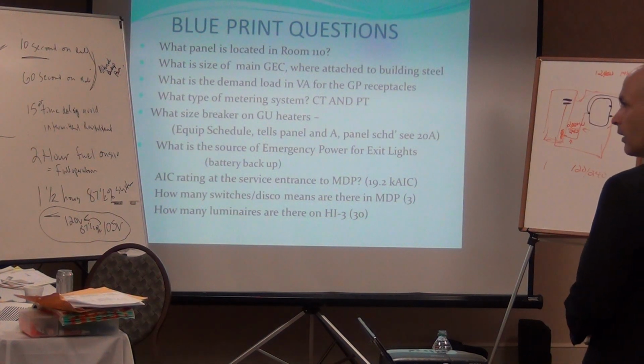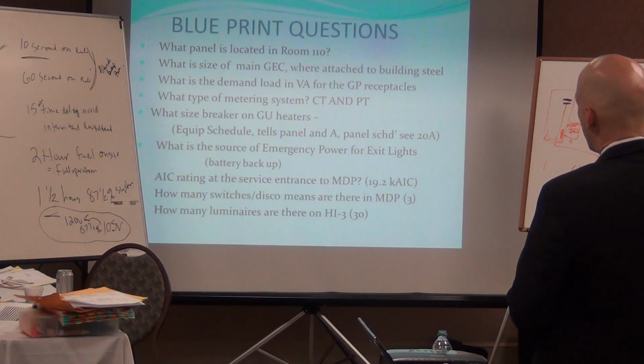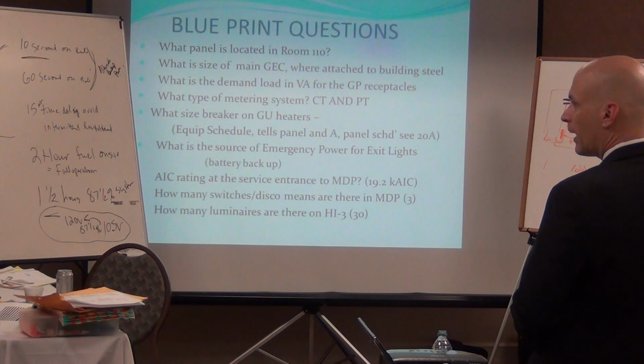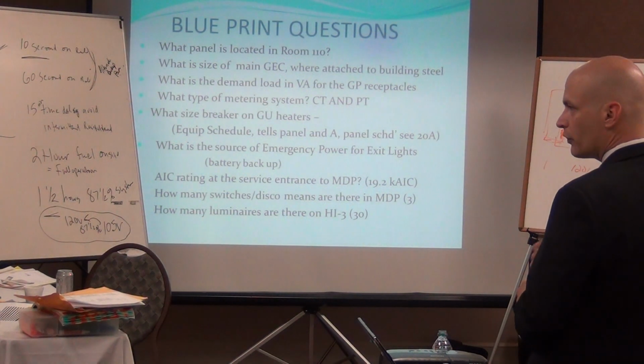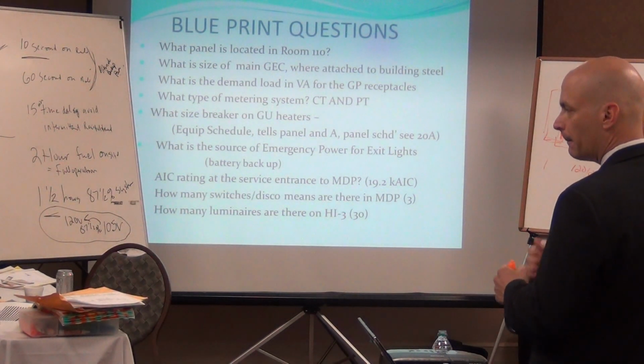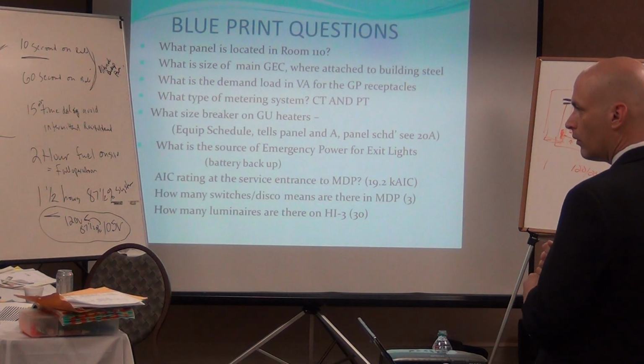I don't know what kW they are. Well, some appliances will have a load on it, like your ranges, your dryers, and heavy electronics, because you've got multiple loads there. A clothes dryer will do that, 240 volts on that, but their controls are 120. So they'll make that neutral current.